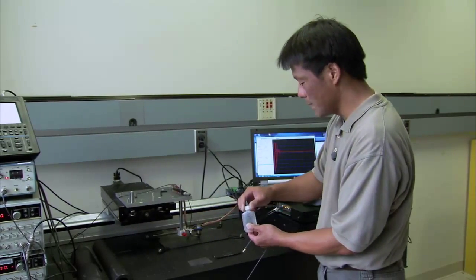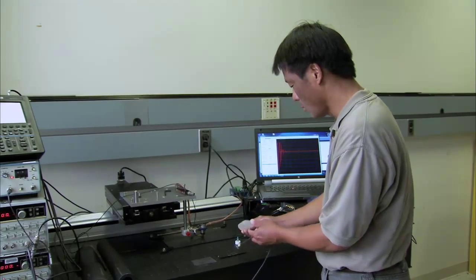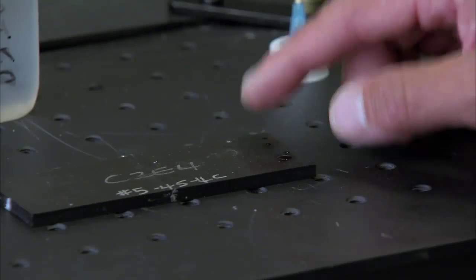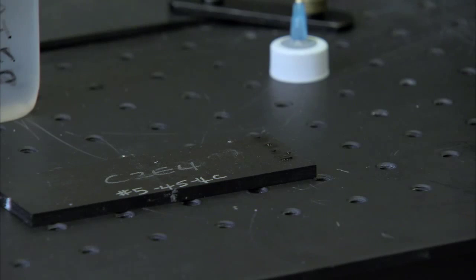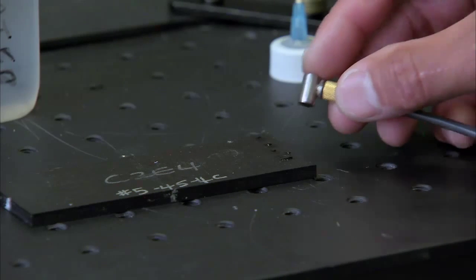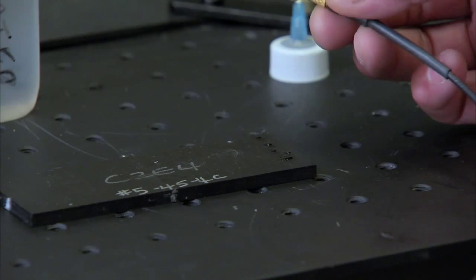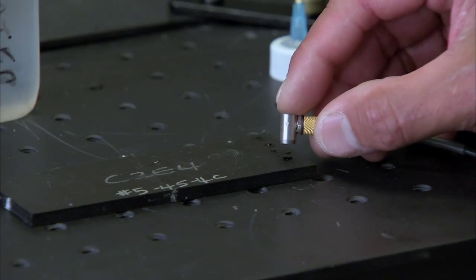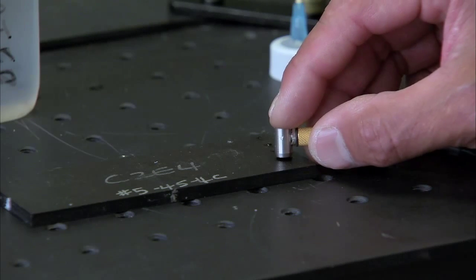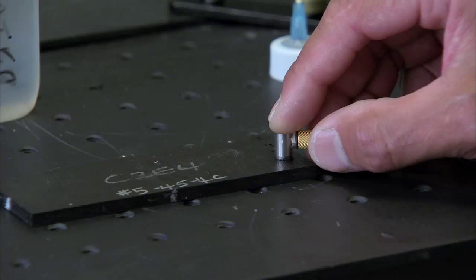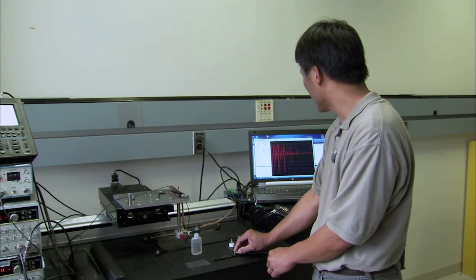So a commonly used medium is water. So I'll just put a little water on the surface. And as you can see, as I press down, you can see the waveform change, showing that the ultrasonic energy is transferring into the sample and it's reflecting back through the sample.